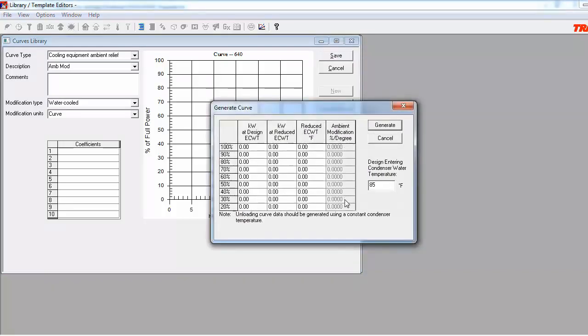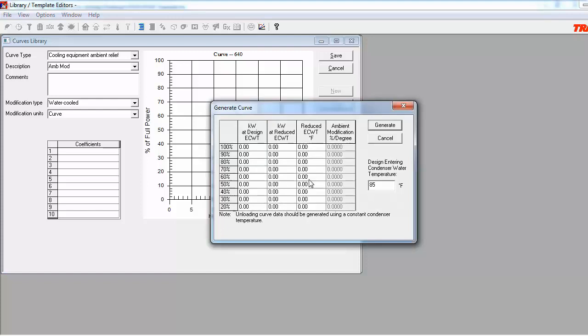In the new window that opens, we can see that the two other columns that were previously grayed out are now available to input data. We still need to populate the data previously entered into the KW at Design Entering Condenser Water Temperature column. But we now also need to input the compressor data for the KW draw at Reduced Entering Condenser Water Temperatures column, and the Reduced Entering Condenser Water Temperature in Degrees Fahrenheit column.